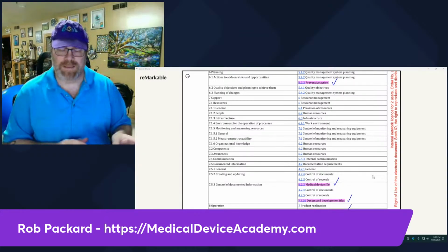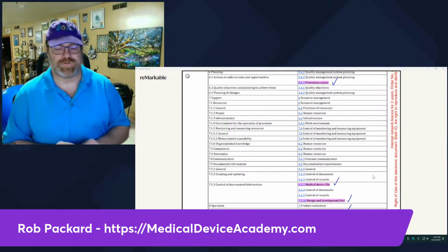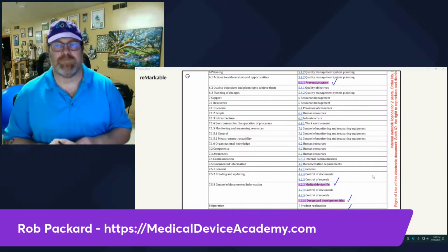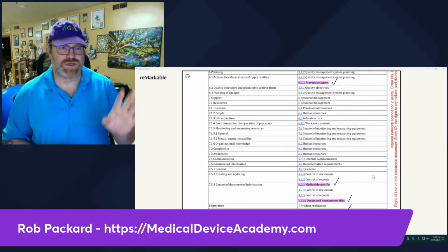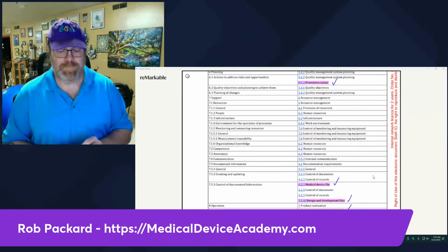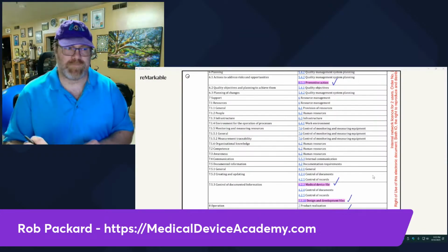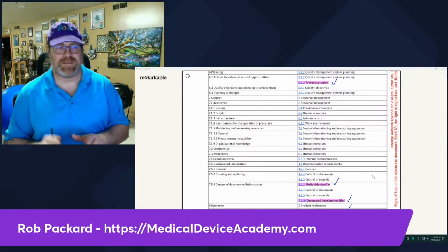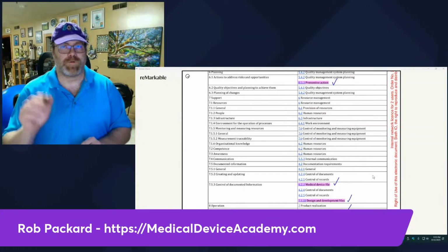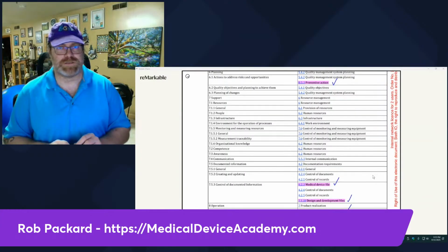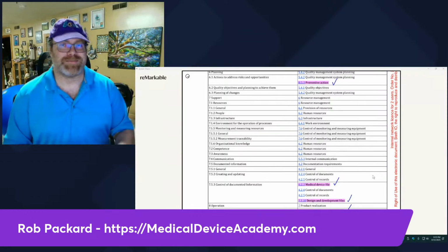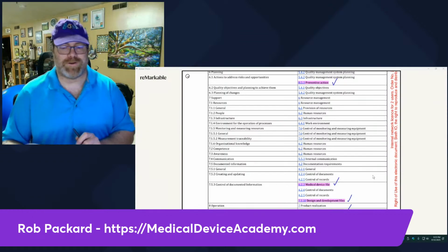So there is a planning section in section 4 of ISO 13485, and there's a planning section in 7.1 of 13485. The planning section in the beginning is quality system planning, which is in both standards. The planning and product realization in 13485, it's a little bit different. Yes, the operational planning and control is the same, but the risk management note that says refer to 14971 for risk management requirements, that's not in 9001, and I'll talk about that more later.